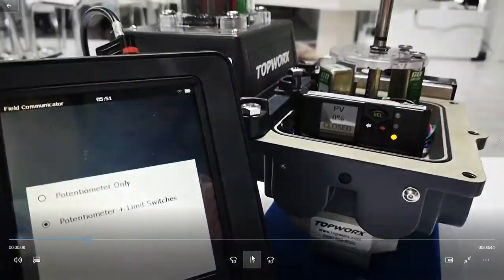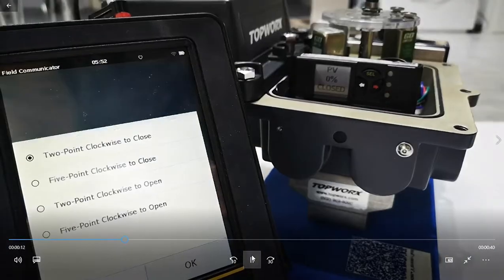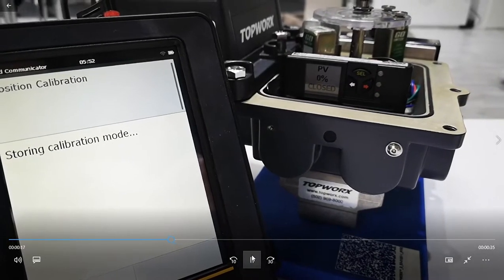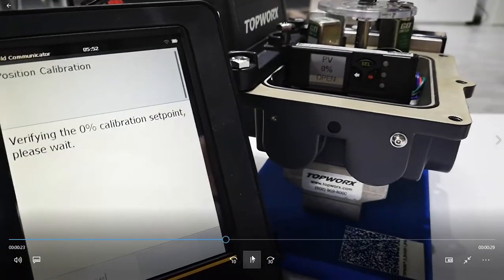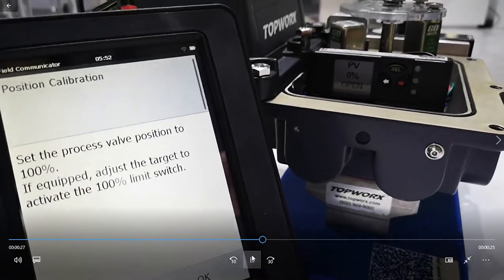This will modify the internal parameters inside the device. It's a potentiometer with limit switches, and we're doing a two-point clockwise-to-close, so we're turning the valve clockwise in order to close it. We're setting the zero position and now we just get the feedback and verify the calibration point.